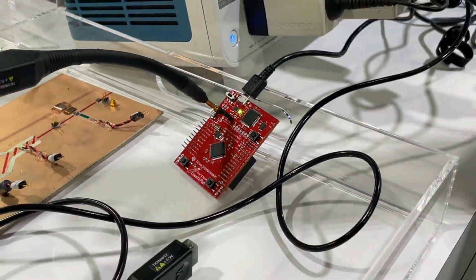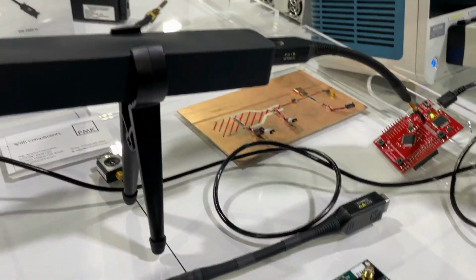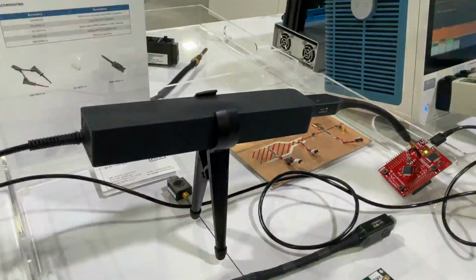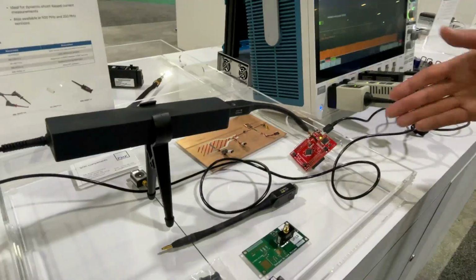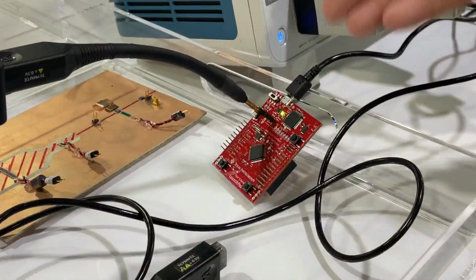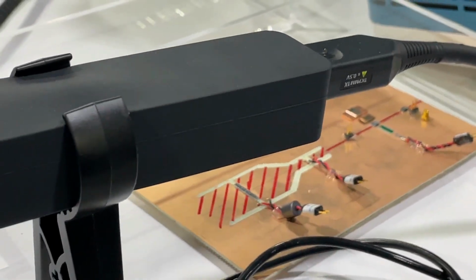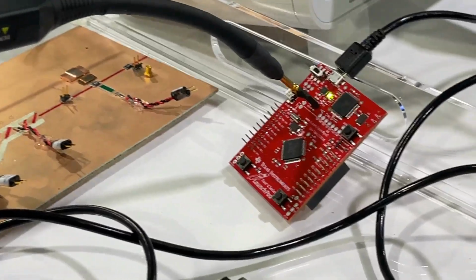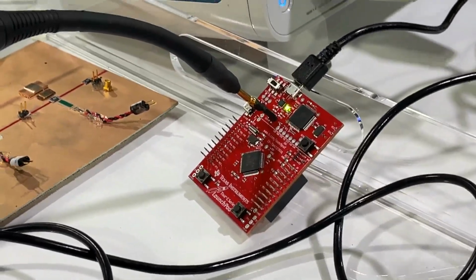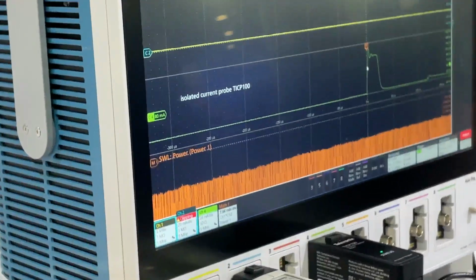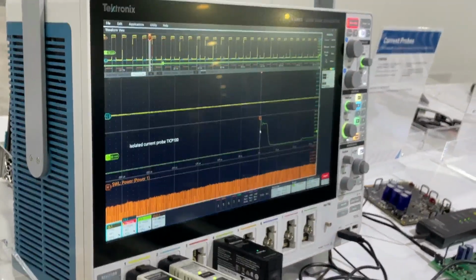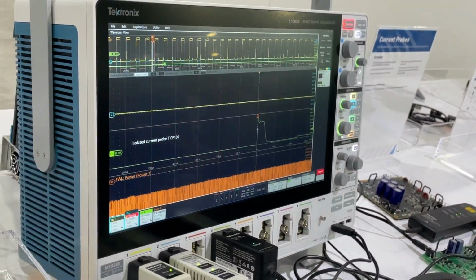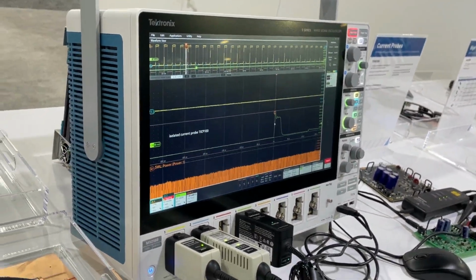So the combination of the RF isolation, it is a 50 ohm path, and we're just hooked up to a demo board here, but this will measure extremely low current. This is our 1x tip with a dynamic range of plus or minus half a volt. And in this example, we found extremely low noise, even as a voltage probe, but for current, it's beating our Hall effect probe and our Rogowski probe.